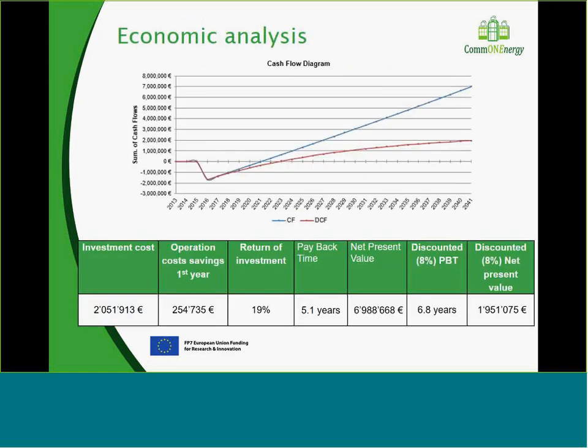Something about the economic analysis. As you can see, we managed to have a payback time of 5.1 years with 0% discount. If we take into account the discount, we have a payback time of 6.8 years. So even in this new building, we managed to propose a solution set that is capable of paying for its installation in less than 7 years.